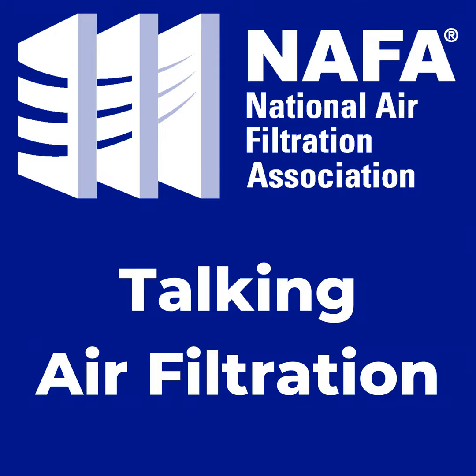So as people get more aware of what's in the air and how they want to protect their spaces with people, you want to look at how we can improve that. So when you compare this MERV 7 nano with electret media, you can see here, the pressure drop increase is a little bit higher. You've got 0.3 for that electret media and 0.4 for the nanofiber media. But we know that MERV 11 with electret technology is going to drop to MERV 9, MERV 8, MERV 7, and that nanofiber media will maintain that efficiency throughout its life.